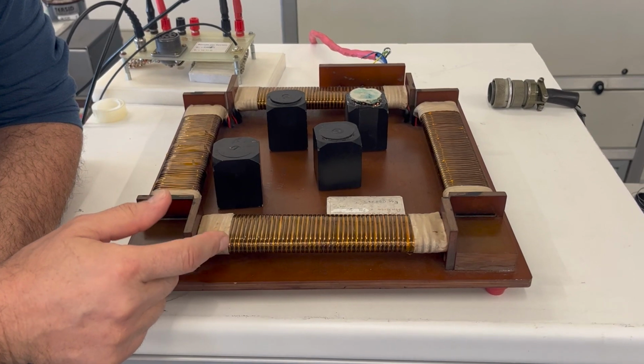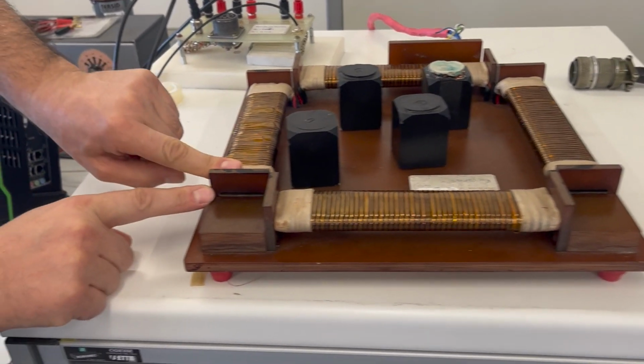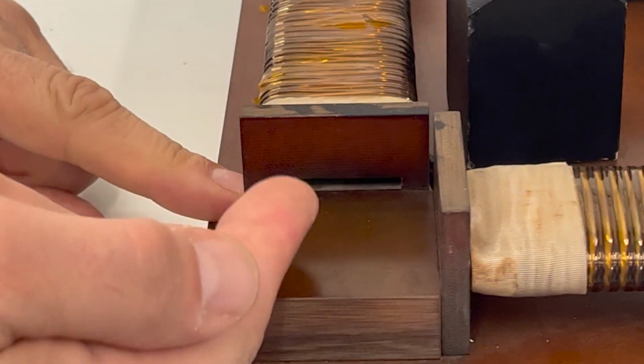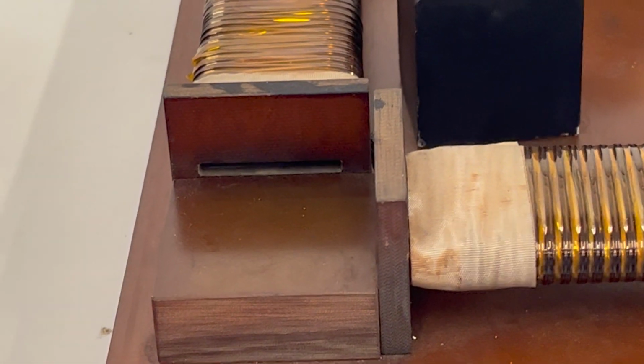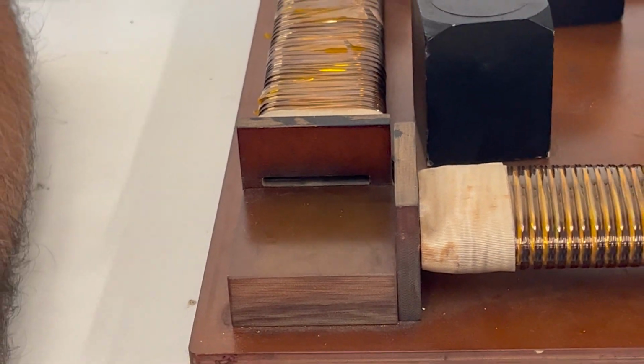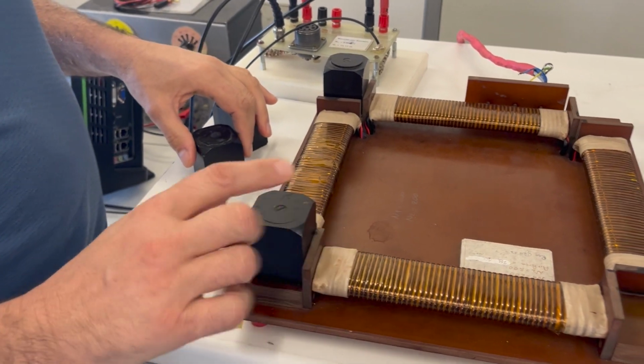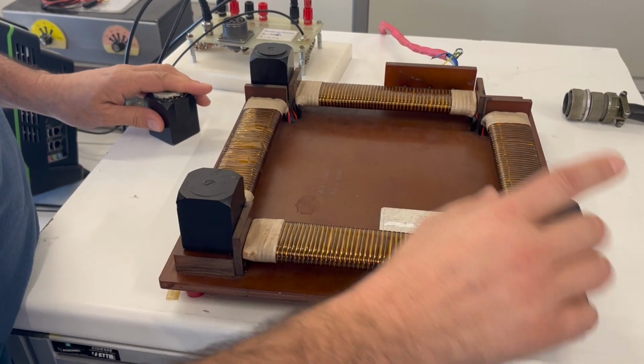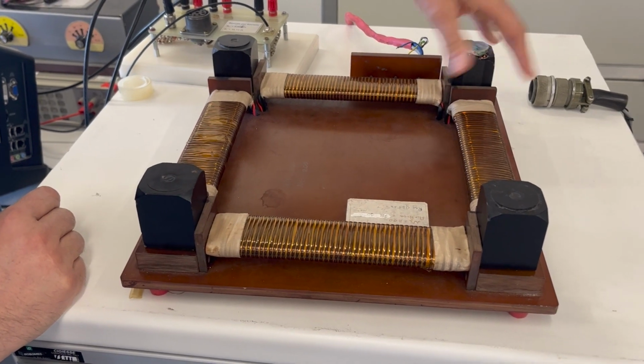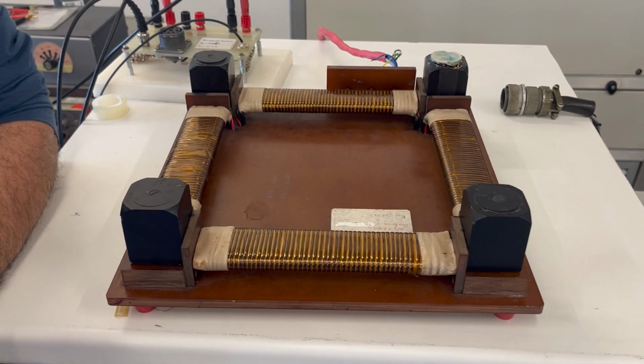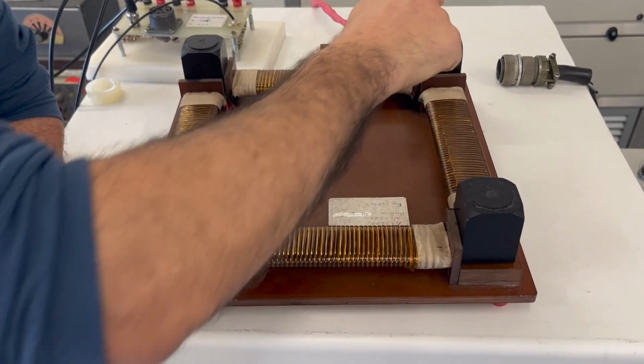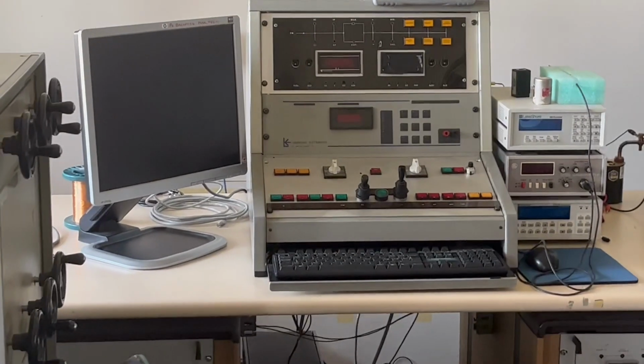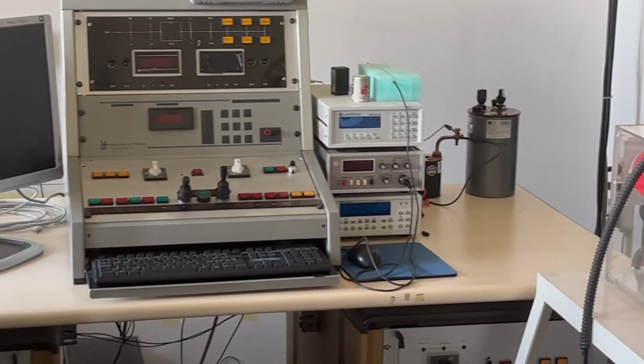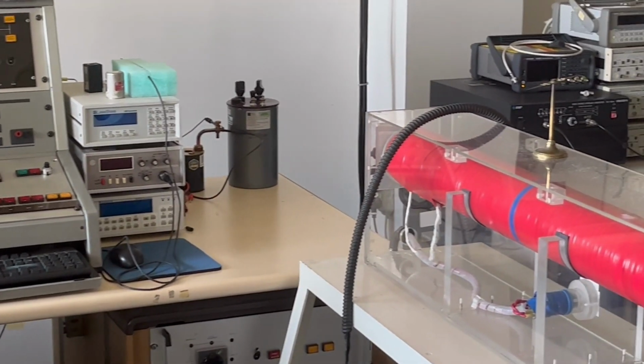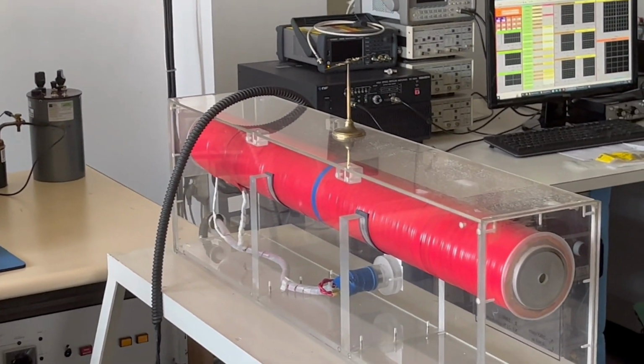The Epstein frame can be made with coils with fewer turns and a smaller gap when measurements instead of DC conditions are done in high frequency. In any case, at the corners where the sheets are joined, blocks of known masses are used to ensure a good magnetic flux closure across the sample. The measurement technique with the ballistic method remains all the time the same, independent of the magnetizing device and of the material under study.